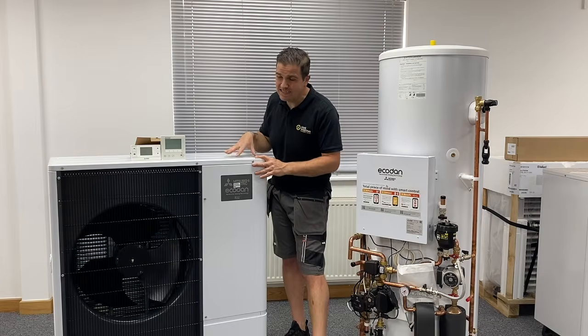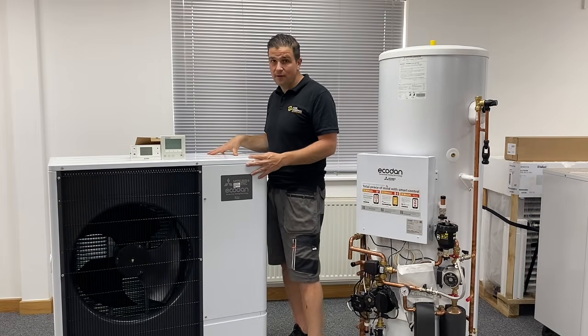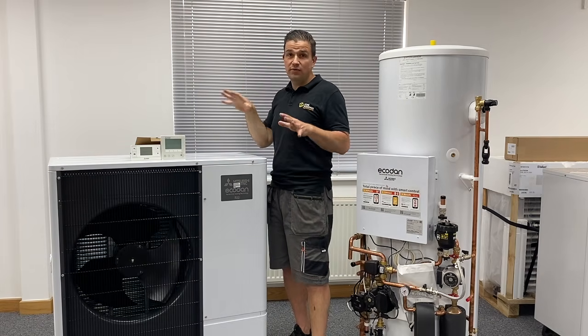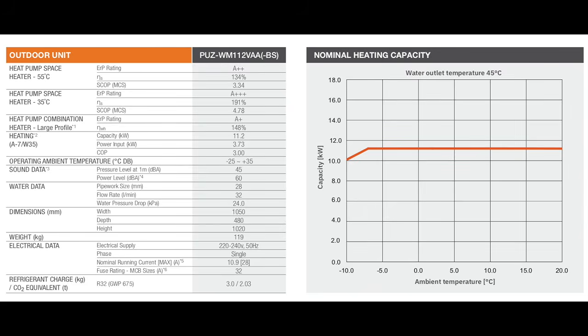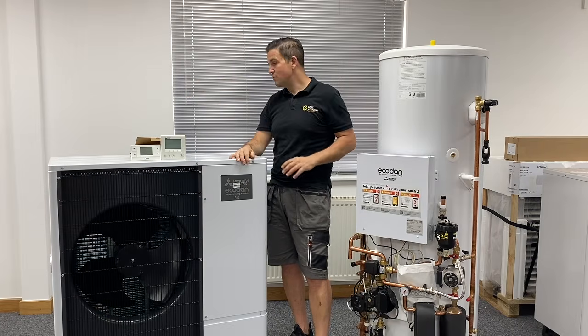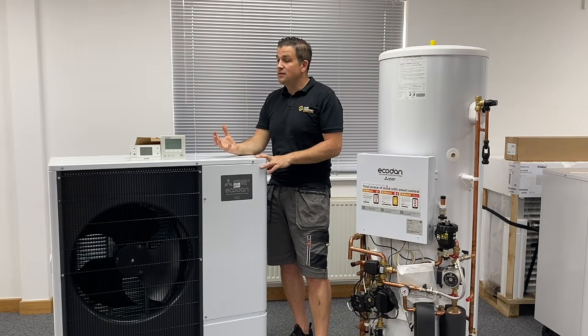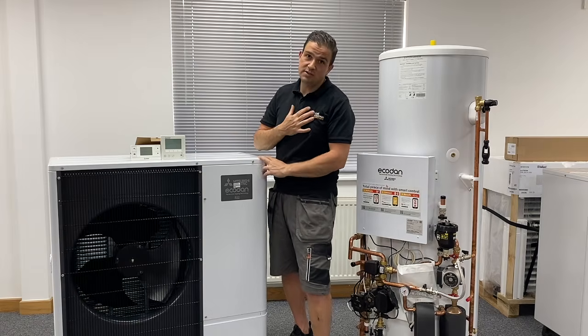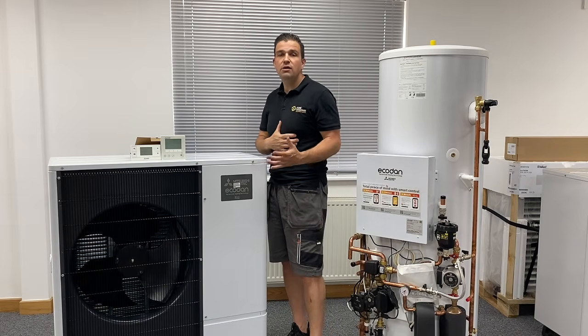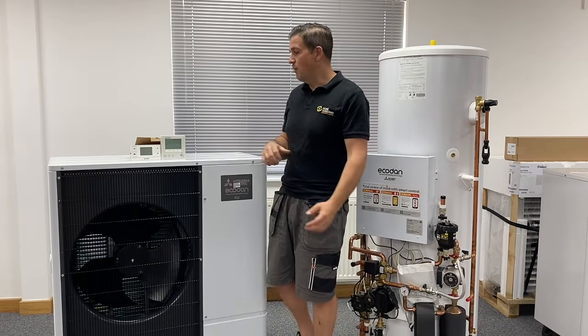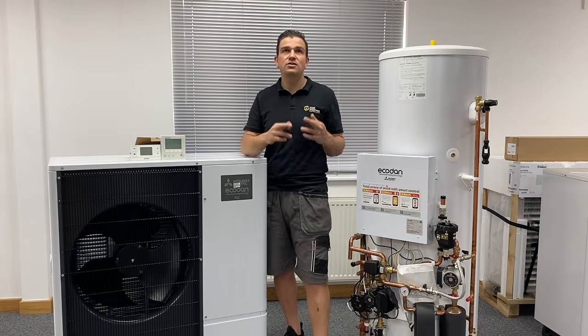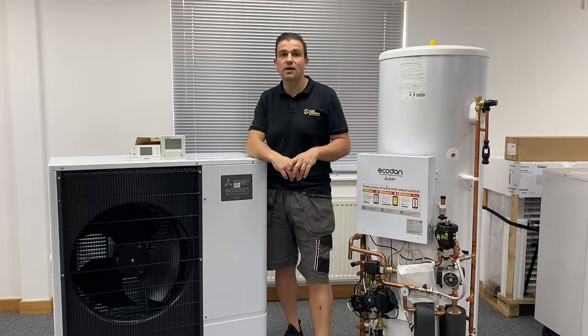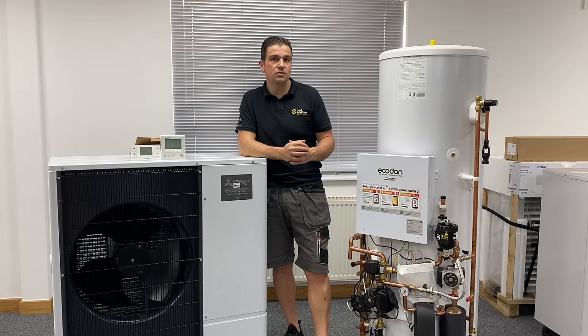Well, the Ecodans, the way they set them up and the way that these units will work, on their data, they show that they're on a level playing field. So at -5, -3, -2, 0, 1, 2, if you've got an 11.2 and you need 11 kilowatts of heat output coming into your building, it will hit on that level and stay there. So that does provide some peace of mind, especially for us as installers, because we need our heat pumps to really perform, especially at the coldest times. What we don't want to be doing is putting something in and then crossing fingers, and no one should ever do that as an installer, just hoping that it's going to be able to produce in the coldest of temperatures.